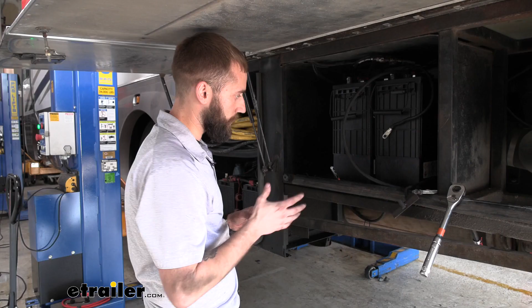Within 18 inches of the battery side, we have to put a circuit breaker in. That's going to help protect our battery in the event that our converter tries to push more than 100 amps, and we're making sure we have the corresponding amperage for that circuit breaker, so I'm putting in a 100 amp circuit breaker.